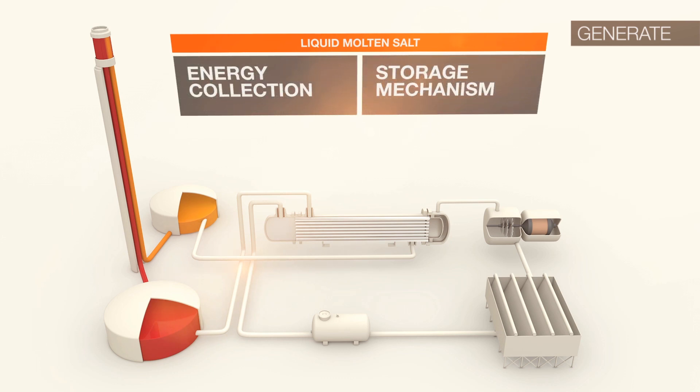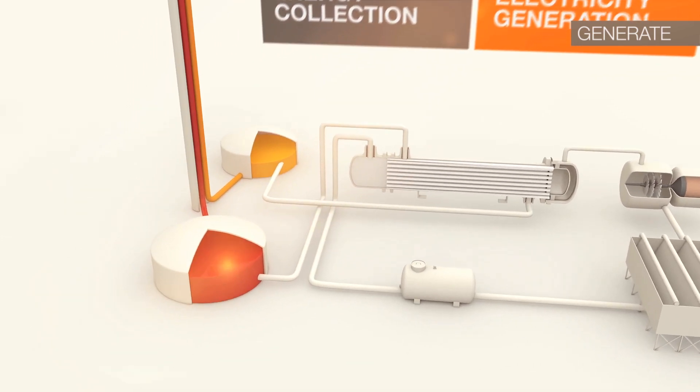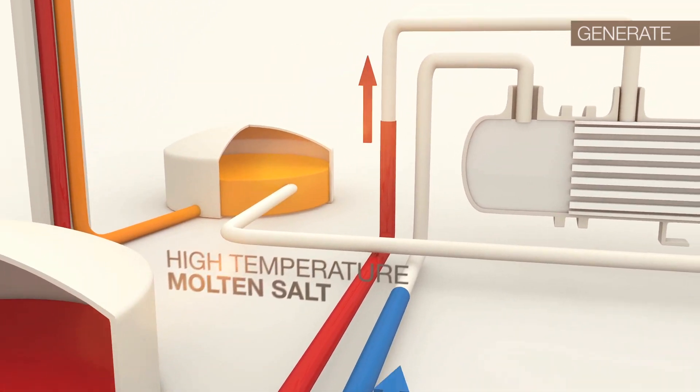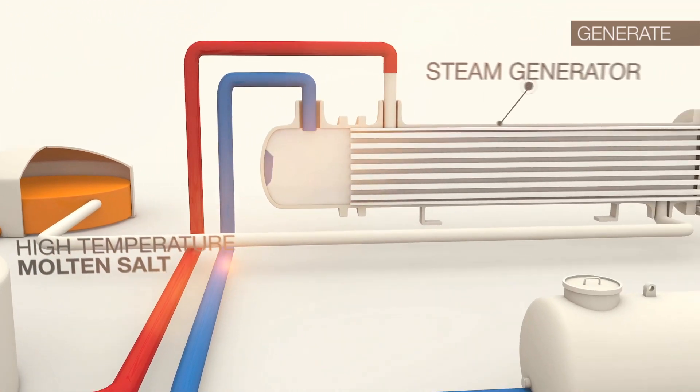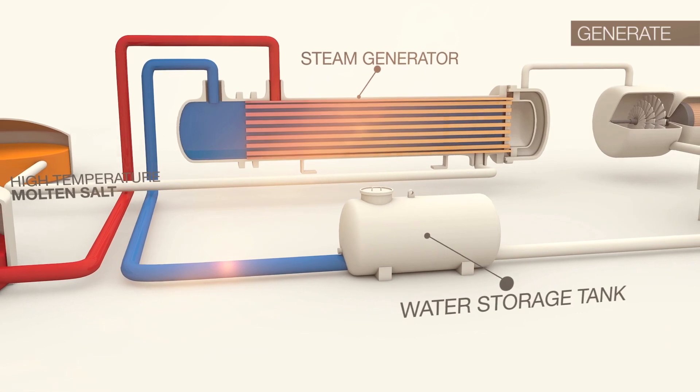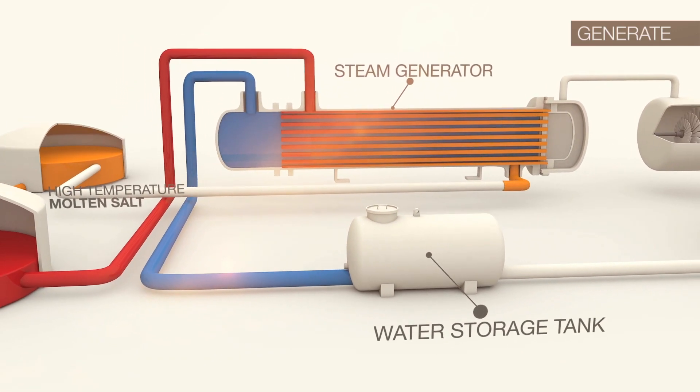Solar Reserve's technology leverages liquid molten salt as both the energy collection and the storage mechanism, which allows it to separate energy collection from electricity generation. When electricity is required by the customer, day or night, the high temperature molten salt flows into the steam generator as water is piped in from the water storage tank to generate steam.